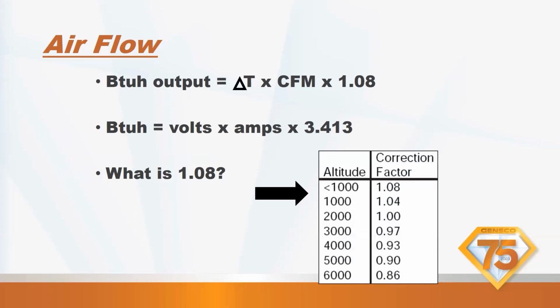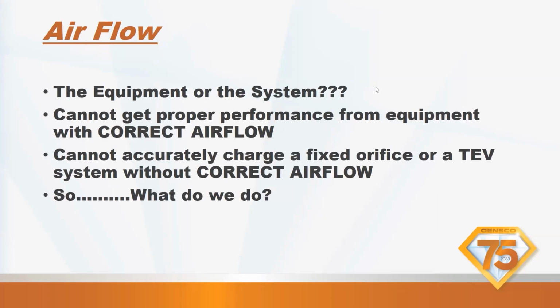These are the BTU output calculations on how to get BTU outputs from delta T times CFMs times 1.08, and it depends on the altitude correction factor. That's what that 1.08 is, in your area where you live. So if you're at sea level, it's 1.08. Where I'm at, 2,000 feet, it's 1.00. And I've got places in Montana where they're at 4,000 feet, so they're doing 0.93. If you're up on the mountain, you need 0.90. So if you do these calculations, do the calculation like this first, use the 1.08.